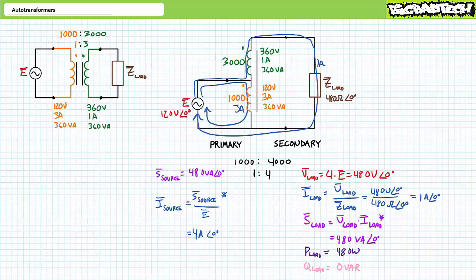Consider the amount of power capable of being transferred by the auto transformer. When configured as a traditional transformer, it was limited to a rating of 360 volt amperes. These same windings configured as a step-up auto transformer allows the device to transfer 480 volt amperes — an increase of 1.33 times — again without exceeding the rating of either winding.